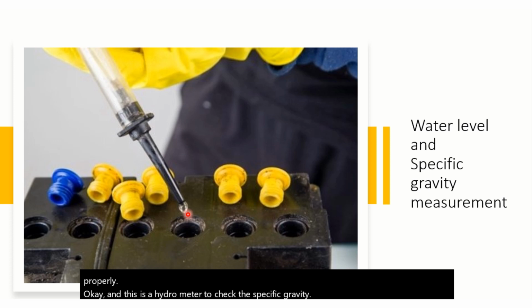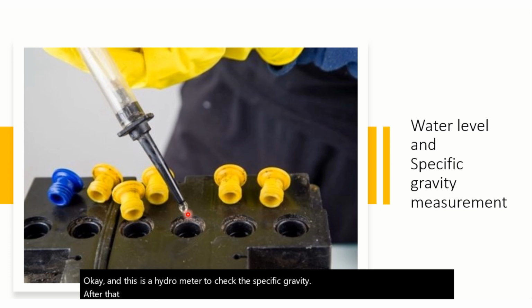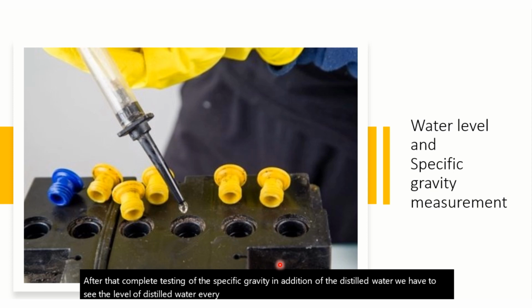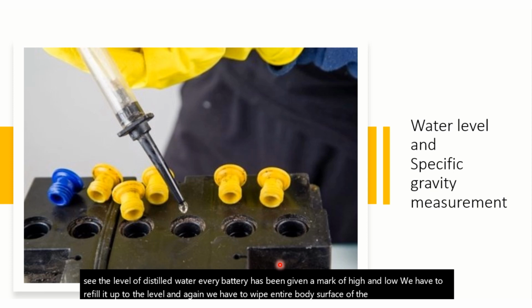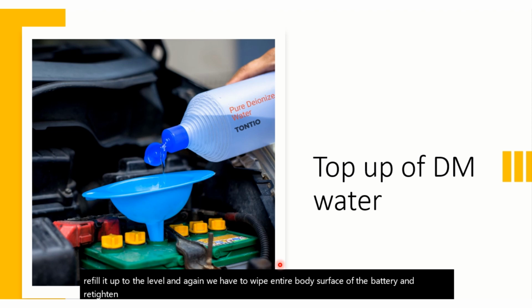After the complete testing of the specific gravity and addition of the distilled water, we have to check the level of the distilled water. Every battery has been given a mark of high and low. We have to refill it up to the level, and again we have to wipe the entire body surface of the battery and retighten the vent plug. Here we see how we are topping up the DM water inside the battery in every cell.